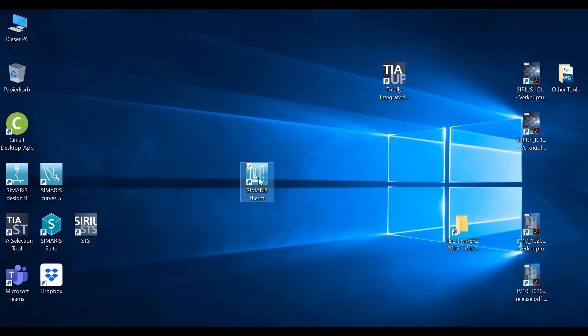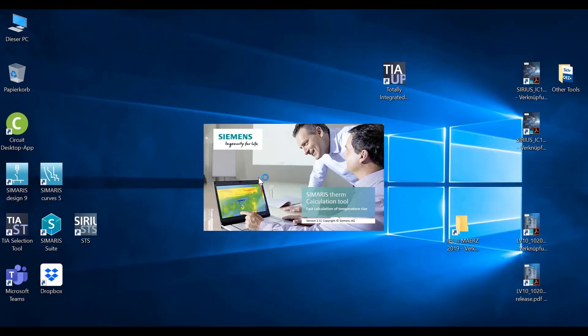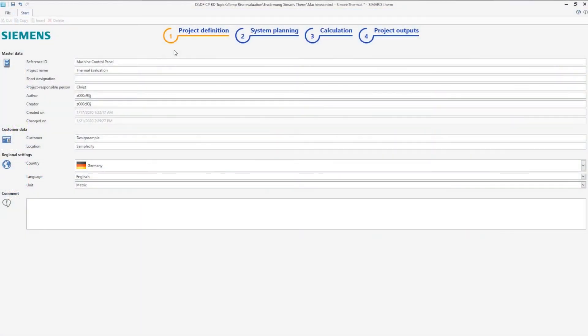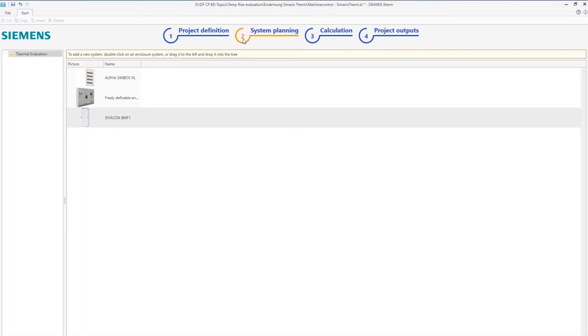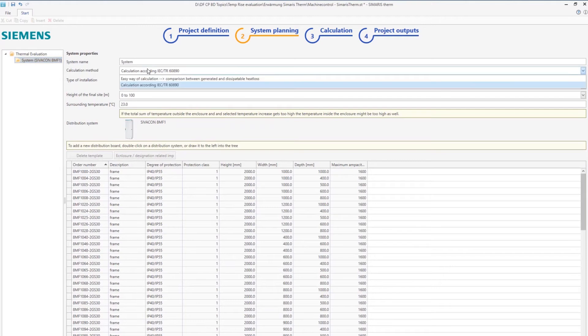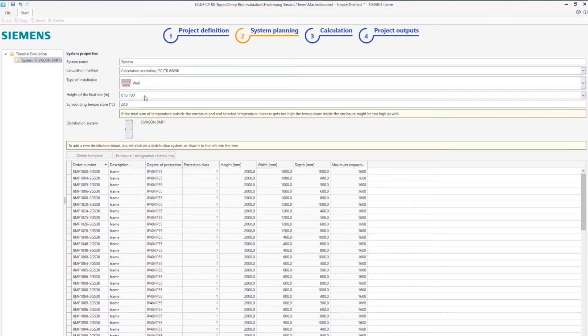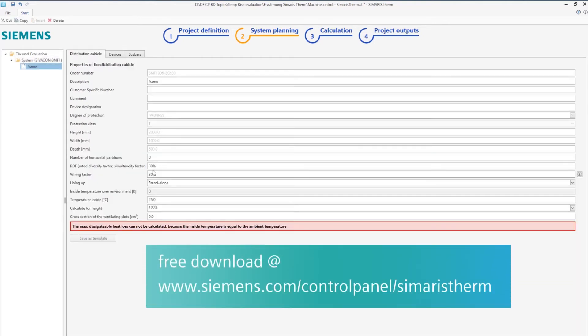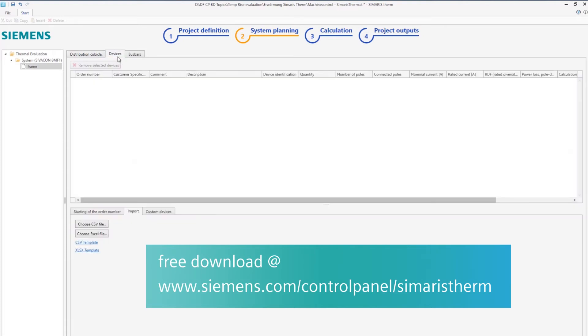With the free-of-charge temperature rise calculation tool SIMARIS Therm, you will be able to combine application-specific requirements efficiently for your machine and control cabinet construction. SIMARIS Therm supports your control panel engineering challenges for various industry or infrastructure requirements. As an electrical designer, you can modify your requirements with regards to installation demands, ambient temperature, installation altitude, degree of protection, and ventilation options depending on your project.